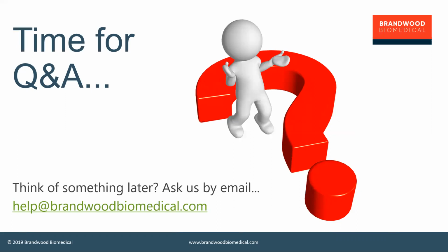Go look at that data set, and if that shows that you're not seeing a particular endpoint you're looking at, then that's actually better evidence than an animal test, which actually is a proxy anyway for the human use. So go look. So the answer, I think, Jennifer, is yes, you might have to justify it, but it's rare that you're going to need to retest. It would be very rare. Look at the history of the device and justify why you've got enough data now that the device is safe.